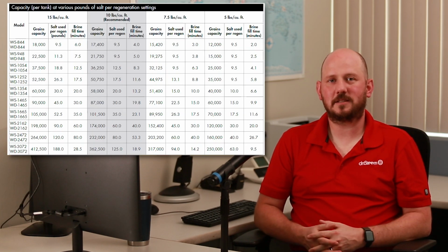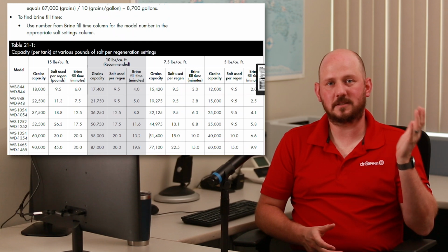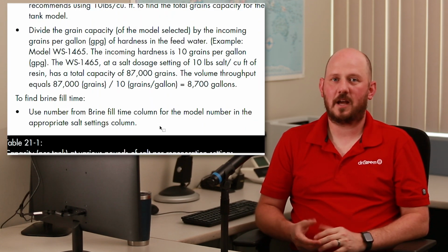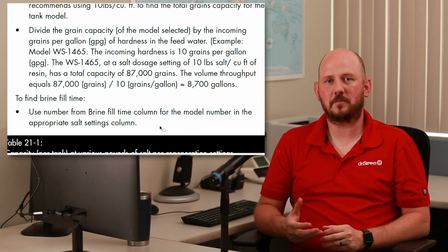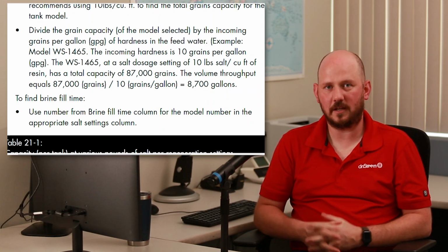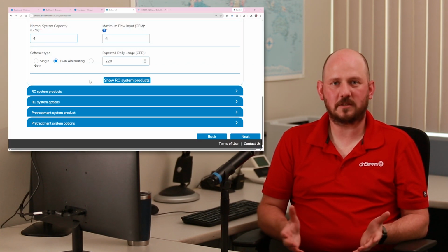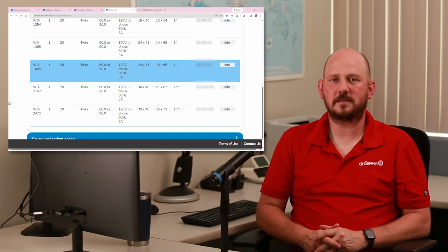As it relates to the component selection, it's pretty standard items. One of the features that I like to mention is how we size and how we apply our softeners and our dechlorinators is through a very transparent communication style, and that's sizing it based on not only the chemistry side of things, whether that's a softener and we talk about the grains of hardness and how much capacity is in that softener, or if we're talking about the mechanical flow rate and the hydraulic flux rate, if you will, or GPM per foot squared. Sizing that accordingly and being transparent. There's obviously boundaries that you can use this technology, and we choose to use variables in our DriCalc software to make this simple and consistent throughout.